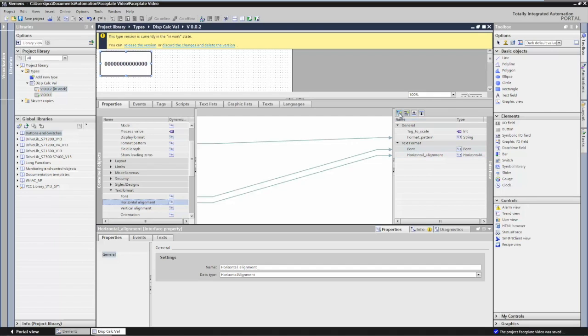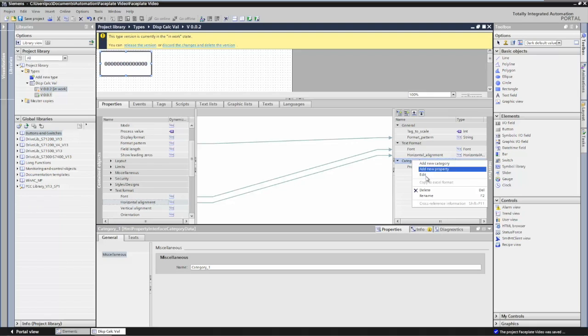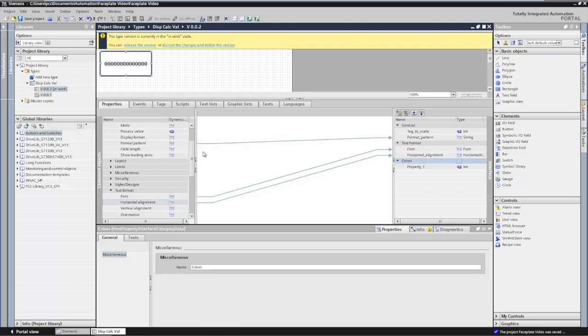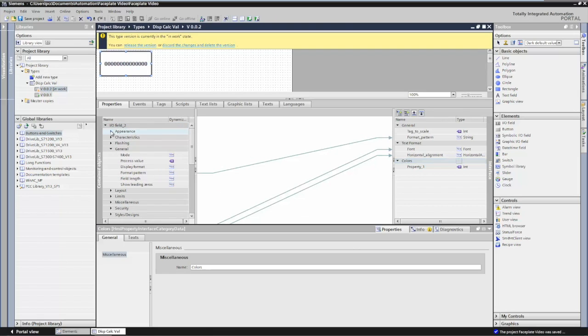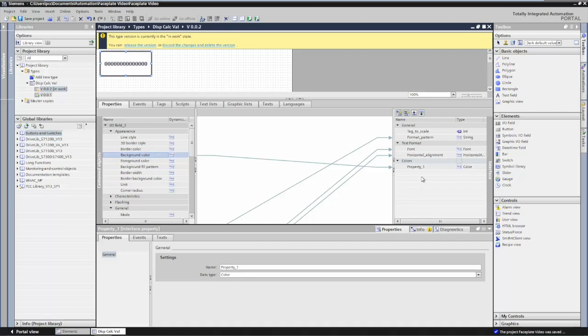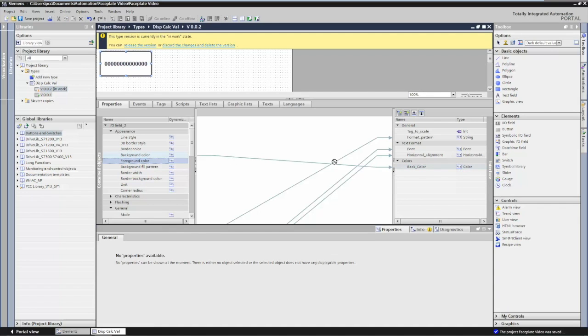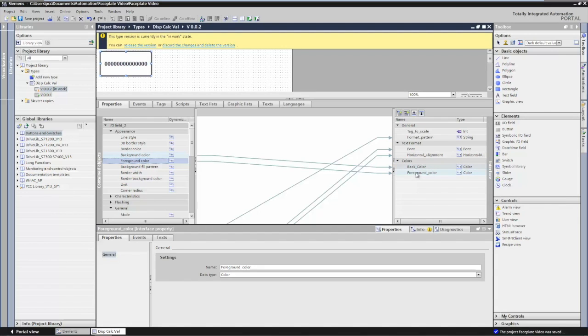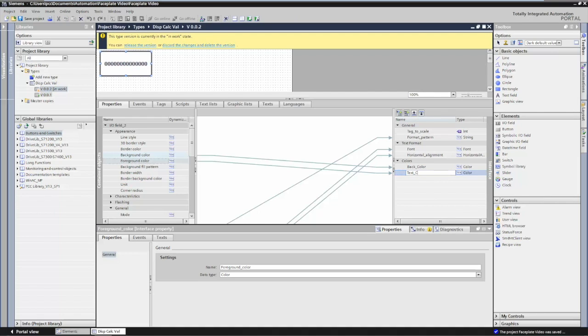The next thing I want to do is add a category for colors. I'll rename the category and call it Colors. I want to be able to change the background color and also the text color. So I'll scroll back up, and under my IO field appearance I'll take the background color and drag that over to the first property. I'll rename it back_color. The next property I want to drag over is the foreground color — I'll drag that over on top of Colors and rename it text_color.